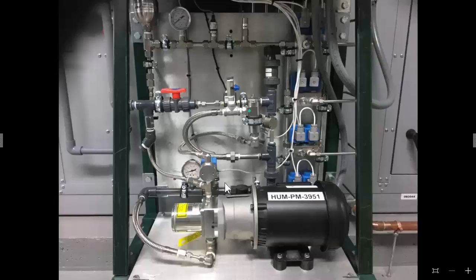And that's actually what is on this pump. Both the input and the output are BSPP fittings. So this fitting right here that comes out of the pump is an adapter that goes from BSPP to National Pipe Thread, NPT. Same with the bottom of the pump. I would like to move towards more JIC fittings, but the components needed to put this together in a JIC format are not as easily available as NPT fittings are.